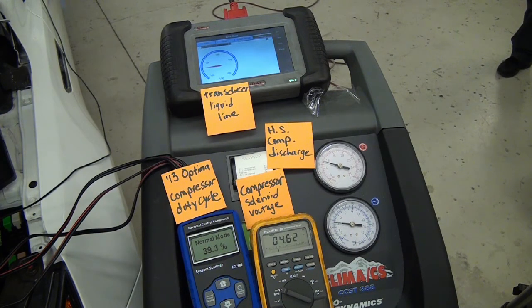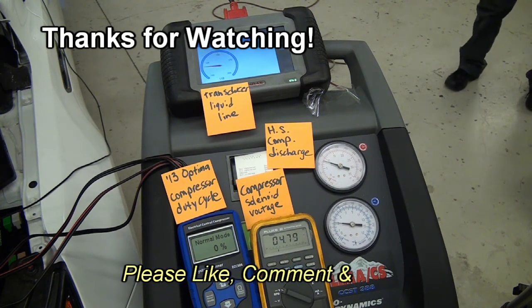Well, it's taken a little bit longer to come back down, but we're pretty close to where we were when we started in the low heat load condition. We're right around 40% compressor duty cycle, about 4.7 volts on the Fluke meter. We're still hovering right around 40 on the low side, and our high side pressure is right around 125. Even the transducer on the liquid line is reading 118.